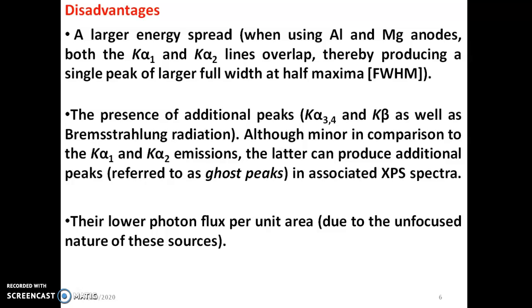Then, in XPS a high photon flux is required to get more photoelectrons emitted. But in the case of a standard source, the photon flux is very weak. Therefore, if we want to use a standard source, we have to work on increasing the photon flux and decreasing the energy spread. So in XPS, the standard source is not commonly used. The standard source is tailored using the monochromating technique, and this is referred to as a monochromated source.